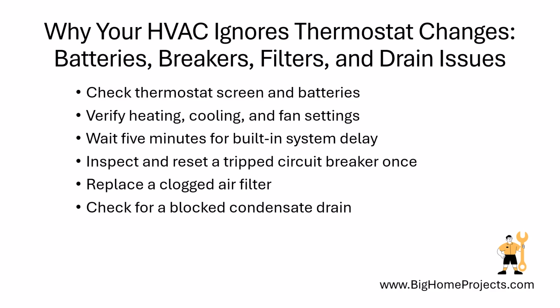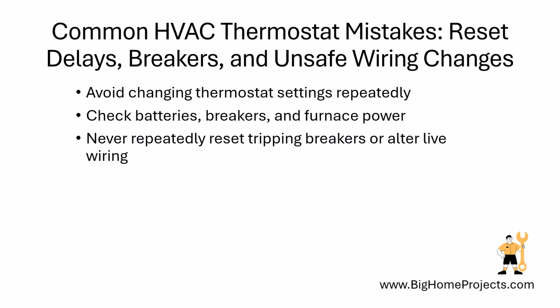If the system makes clicking sounds, runs continuously, smells like burning, or trips the breaker again, turn it off and contact a qualified technician. A common mistake is changing the thermostat setting repeatedly, which can make the built-in delay seem like a failure, so wait 5 minutes before testing again. Another mistake is assuming a blank thermostat always needs batteries, because some models receive power from the indoor unit, so check the breaker and furnace switch too.